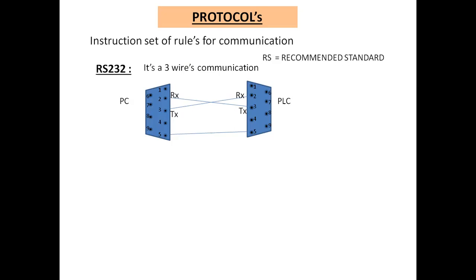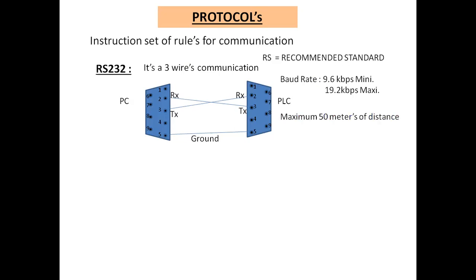So your data should not be lost in between, and for that they have grounding. The last pin, number five, is used for ground. This protocol also defines at what speed it can transfer data. The minimum baud rate is 9.6 kbps — kbps stands for kilobits per second — and maximum it can go up to 19.2 kbps.